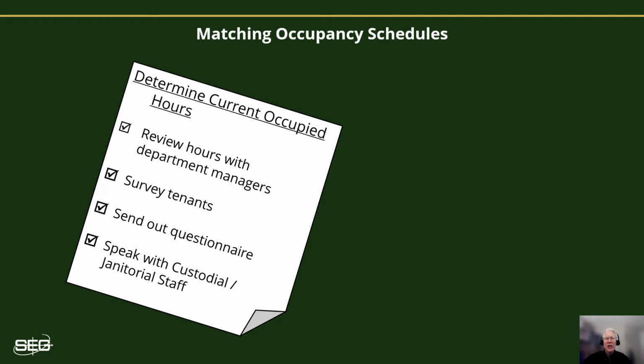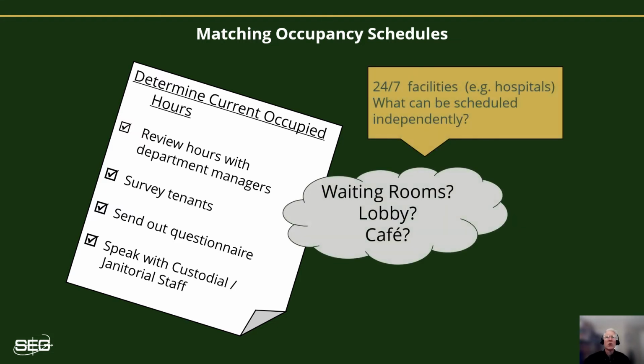And consider each day of the week individually, because the daily hours of occupancy for Monday through Friday may not always be the same. Also look at the different areas of the building for additional scheduling. Maybe some areas can have their HVAC started later than others or shut down earlier. And don't ignore what might seem like a small savings opportunity, such as reducing run time by 15 minutes or so. It may not sound like much, but it can certainly add up over time.